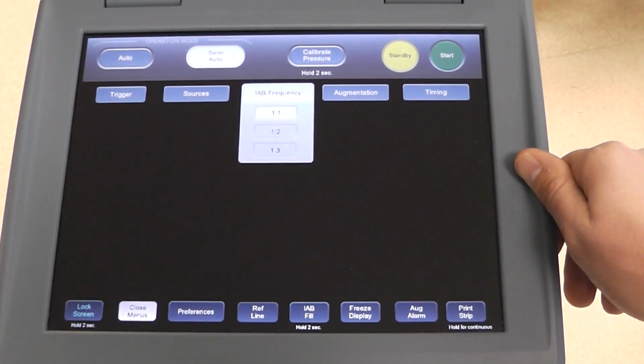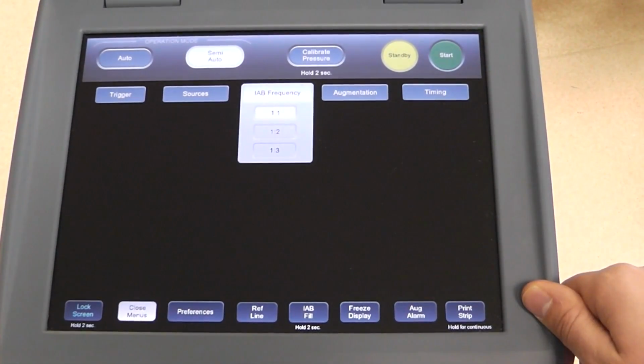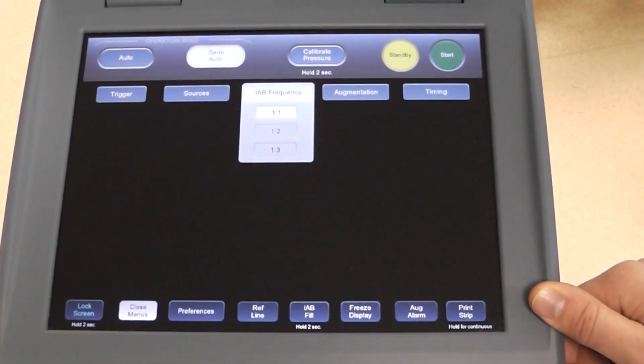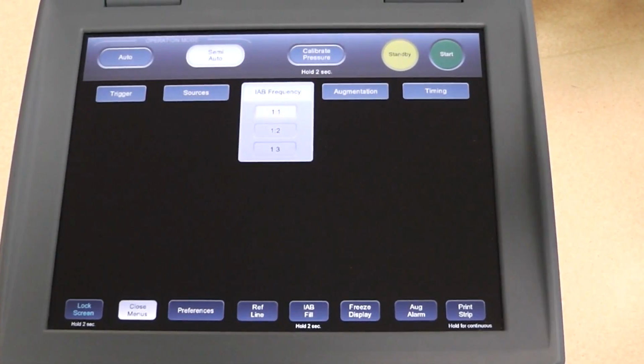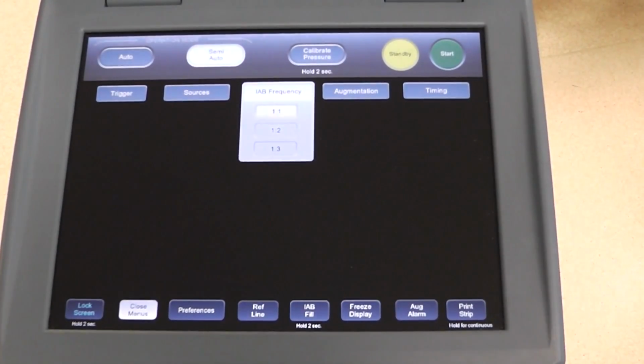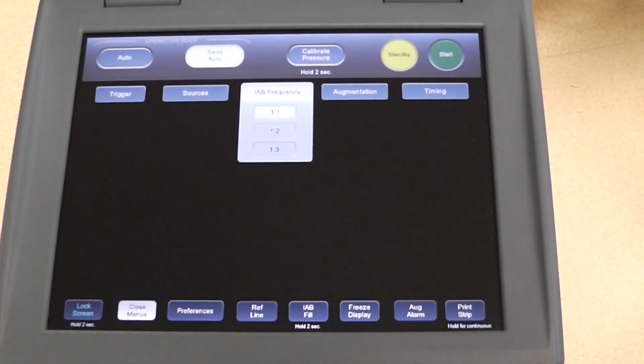Now under IAB frequency, we have three options: 1 to 1, 1 to 2, or 1 to 3. What this allows us to do is to set a ratio of trigger points to balloon inflations. So when this is set to 1 to 1, every time that there would be a trigger point, the balloon will inflate. When it's 1 to 2, the balloon will inflate every other trigger point, so essentially every other heartbeat. And with 1 to 3, of course, it would only inflate every third trigger point.